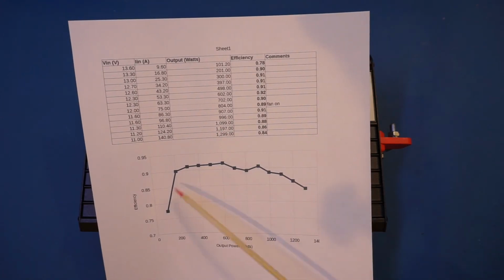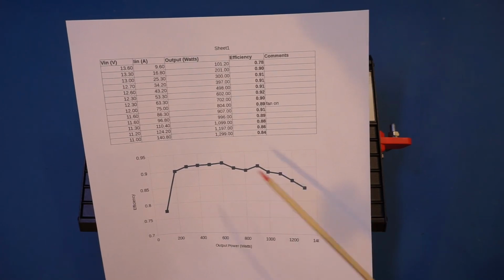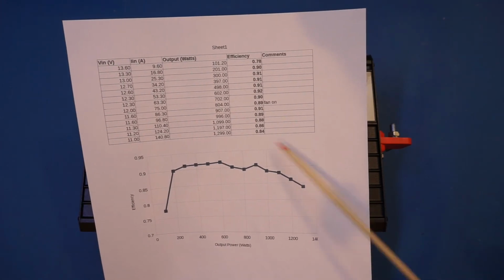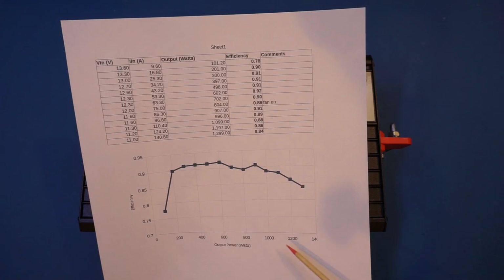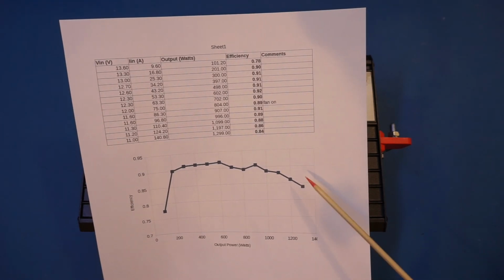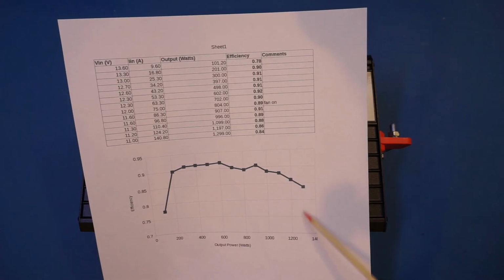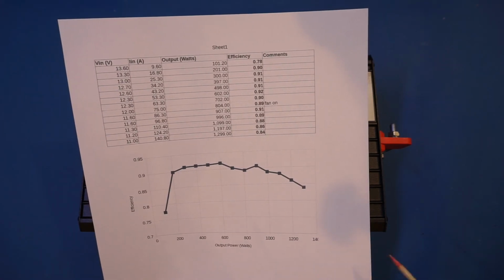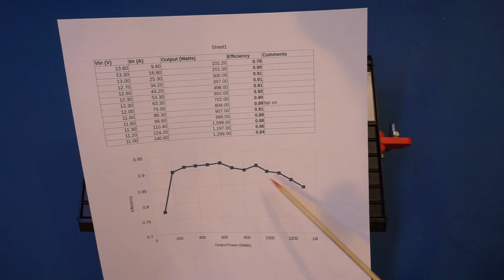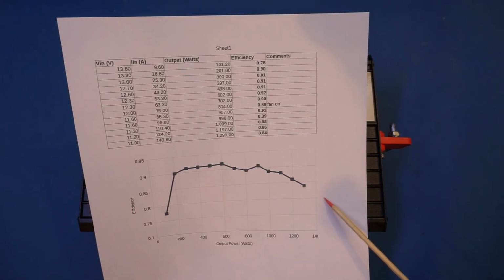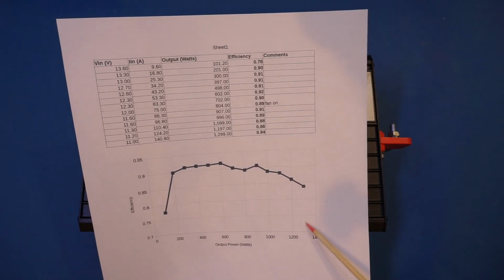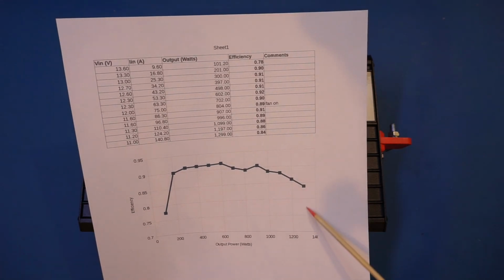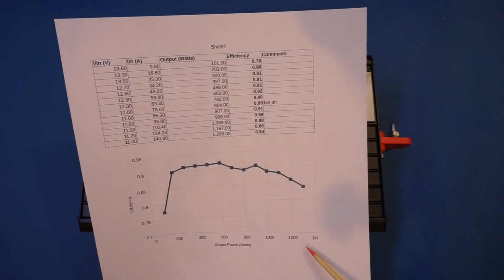Towards the lower and higher ends, the efficiency drops off. From this curve, it seems this inverter is rated somewhere around 1300 watts rather than the claimed 1500 watts, as the efficiency drops off there, and that's also where we got the cutoff warning that it's exceeding its maximum capacity.